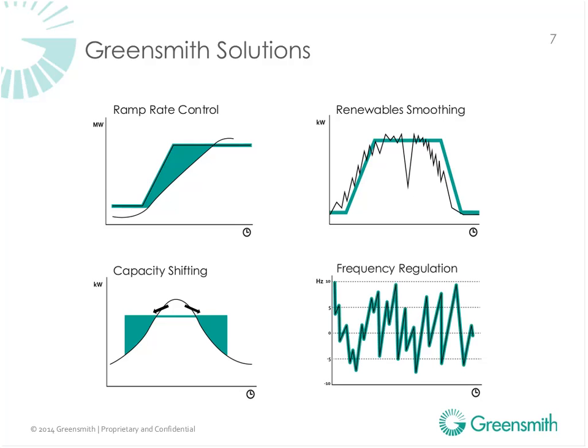distributed batteries into the local field, you have also put an inverter there. And there's a whole host of functions on VAR balancing that you kind of get for free. What I mean by free is that a lot of people, when they're building their economic cases on how to site storage and how large to make a storage unit, you have to buy an inverter anyway because storage is DC power and the grid needs to be AC interconnected. So you need to do the conversion from DC to AC. So the inverter is sitting there and has to be used.